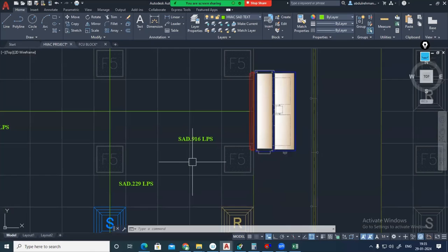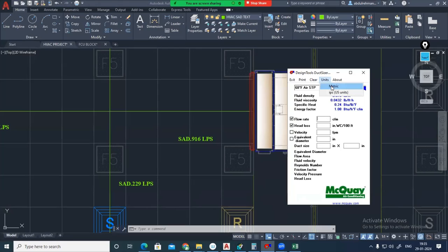For example, I'm selecting this one. I'm changing the unit into metric. Flow rate is 916 liters per second. Head loss, I am considering 0.8 pascal. Equivalent round duct diameter, I'm getting 454. Fluid velocity is how much? 5.6. Okay, right.